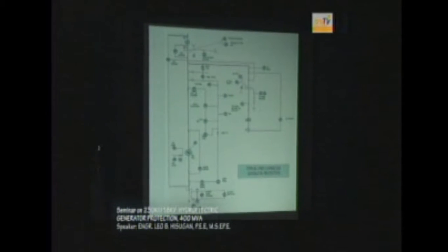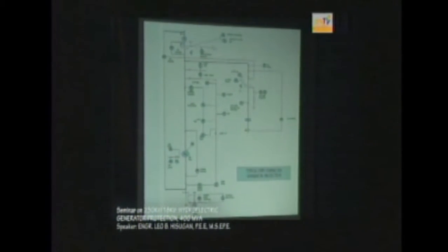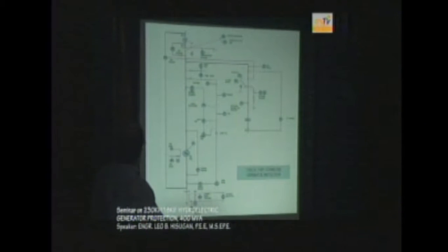This is the generator here. So we have this generator differential transformer 87G, and also we have this high side overcurrent here. The 27 device is your under voltage relay. The 78 device is for your loss of synchronism. The 32 device is your reverse power for your anti-motoring. The 49 device is your thermal protection, right?